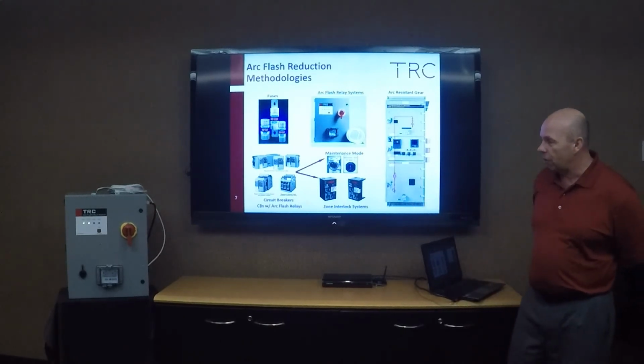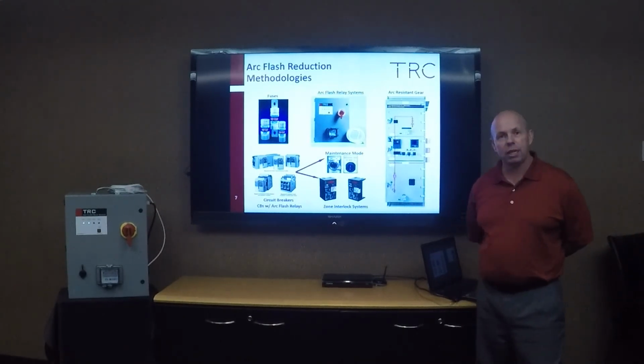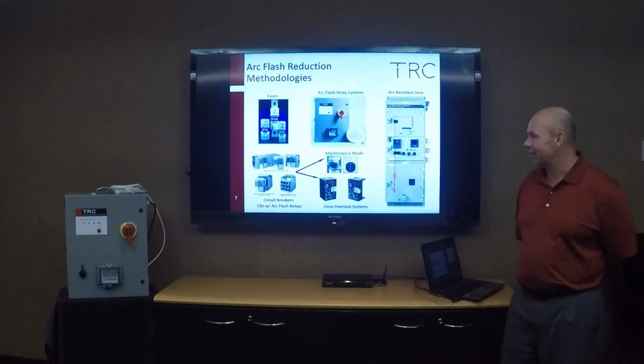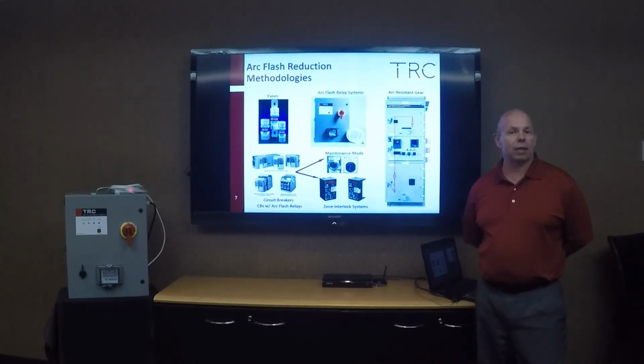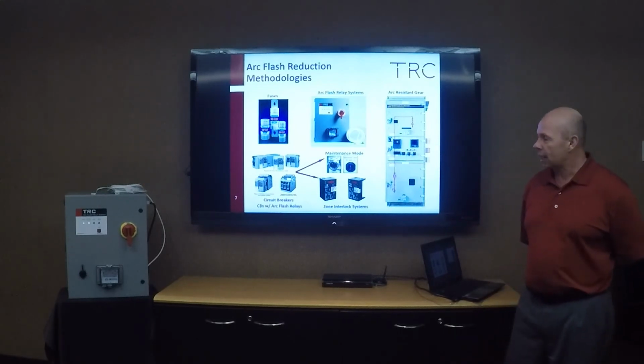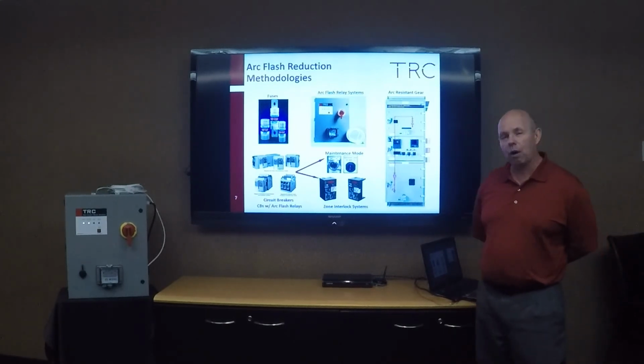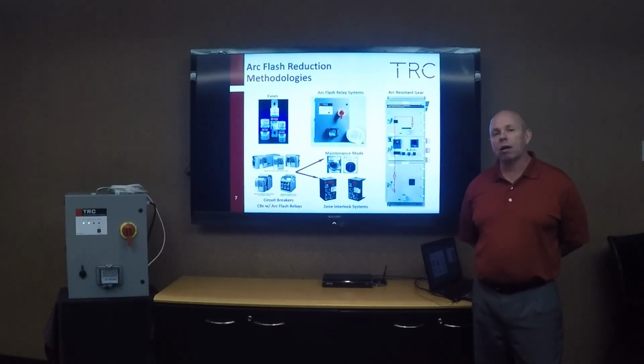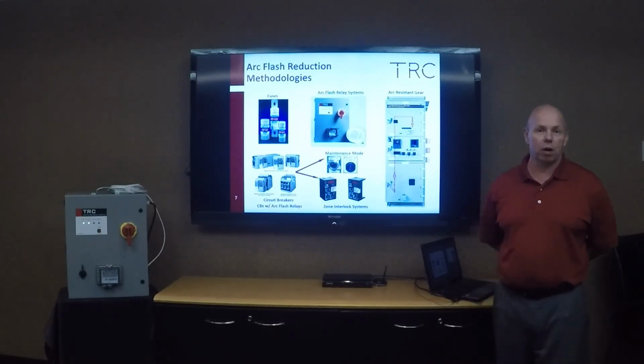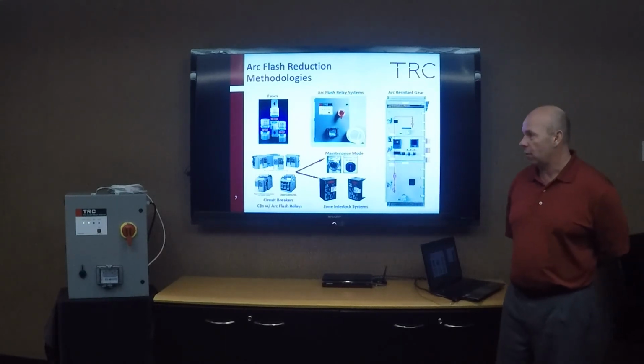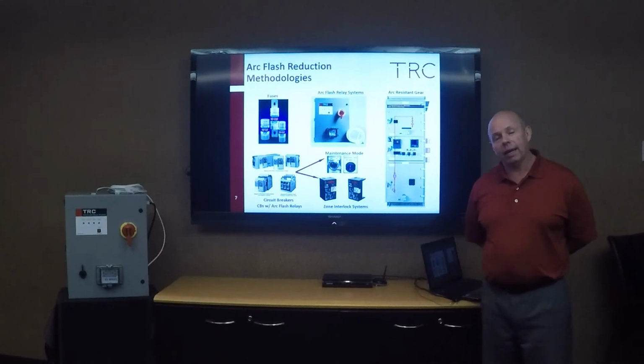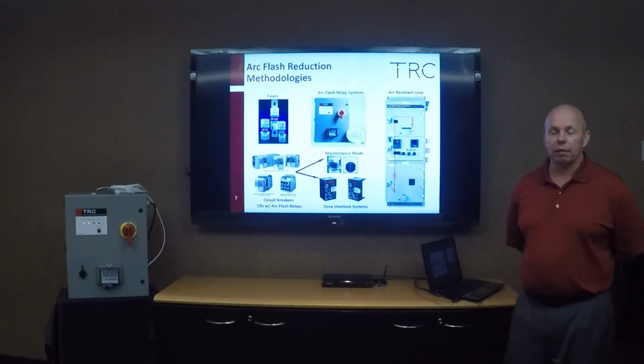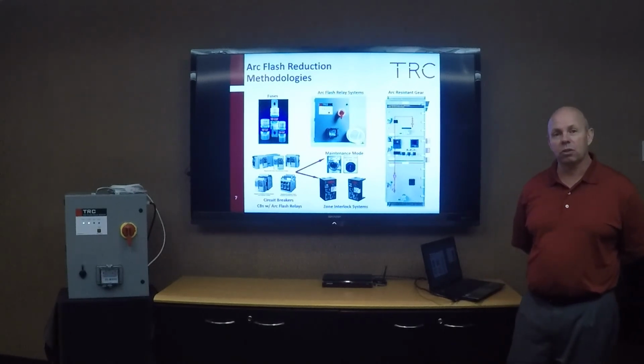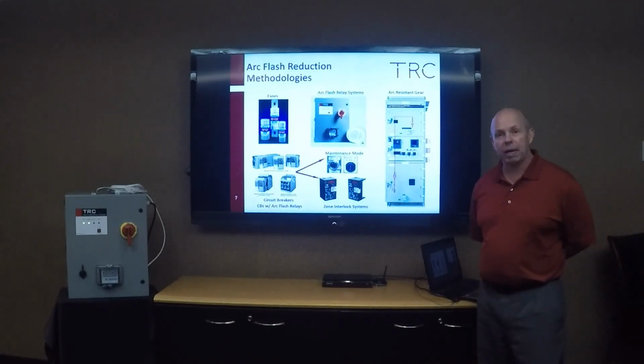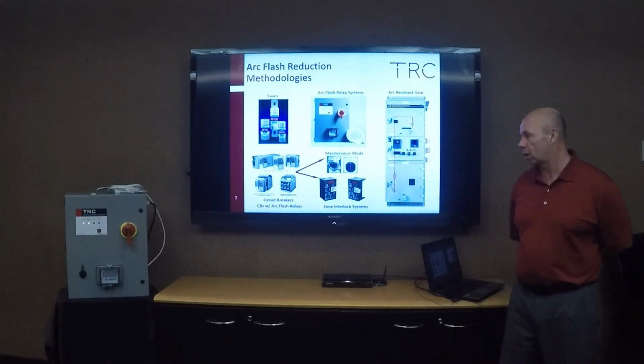And I have a picture, we have a unit over here. This is the TRC P1 arc flash relay system. This device is intended to go on existing power systems. And we connect up to it through external power, which powers the device. And then we feed our trip mechanism into the shunt trip of a molded case circuit breaker. And that way we can detect an arc flash and then trip the circuit breaker that feeds the electrical gear, thereby reducing the incident energy and making it a little bit better workplace for our people that have to work around energized circuits. So let's talk.